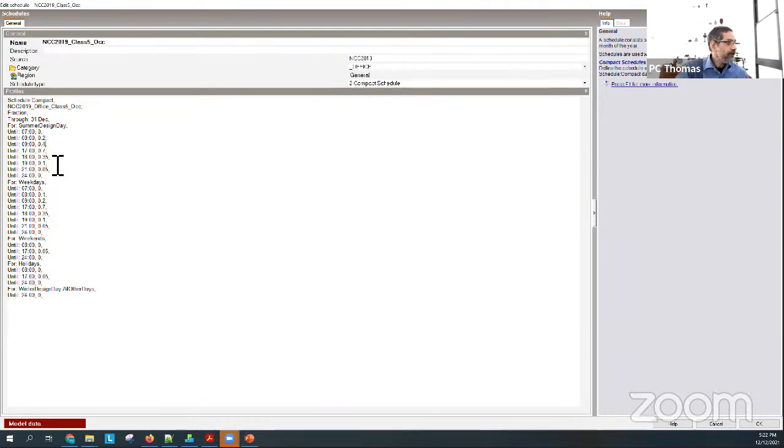And for that time period, when it's critical, I'll say 100% occupancy during that time. Okay. And that'll ensure that the system that I design will take care of the worst case scenario. And just to remind myself, I will put a DD over there. Everything else I'm leaving the same. Okay, just for the summer design day, it will run occupancy like this.